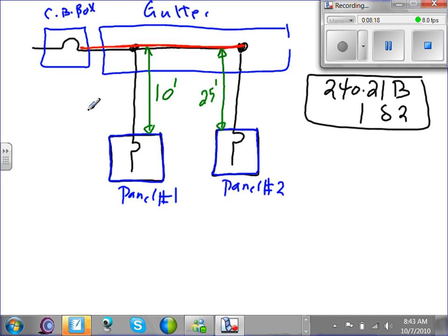So 10 foot, number 1 is 10 foot. Number 2, guys, it has to terminate. The tapped conductor has to terminate in an overcurrent device that does not exceed the ampacity of the conductor. Tapped conductors, number 3, you have to protect them with a conduit from the time that they come out of the gutter all the way to the time they get into your area. So we put the conduit here, Chad. Hey, don't worry. Here's my conduit, right?